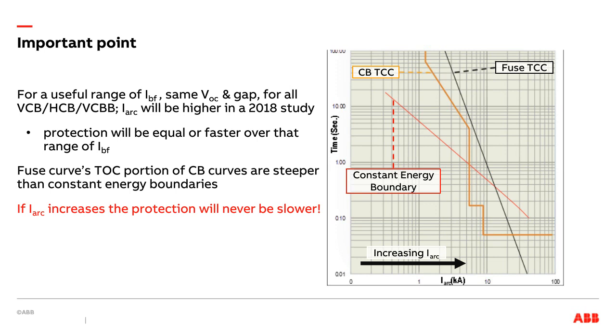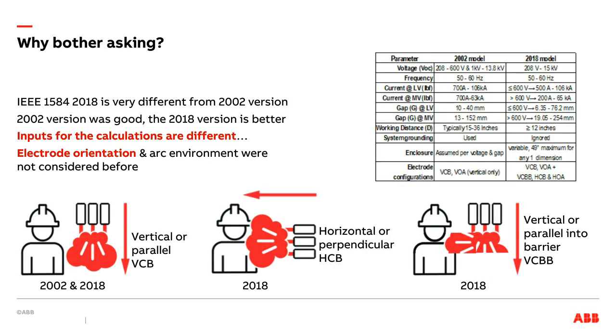The main one is this electrode orientation, that first chart, this thing in the bottom here. That is probably the single biggest potential change. In the old model, it was all vertical. In the new model, it could be one of these three. And these make potentially a huge difference. If you're automatically assuming VCB all the time, you have to be doing a new arc flash study bordering on a waste of time. You really need to evaluate whether it still is VCB, it still is HCB, and still is VCBB. If you have situations where your gap is significantly larger than what you originally used, that would probably bear some consideration for changing.